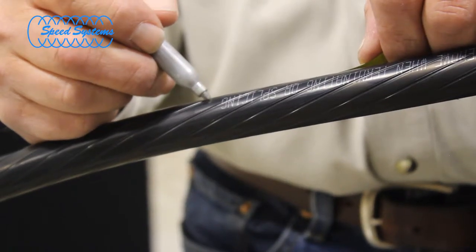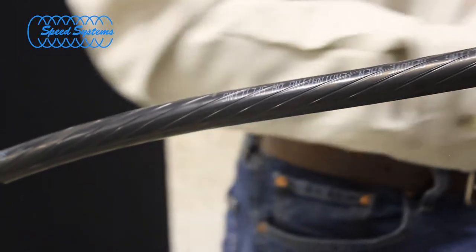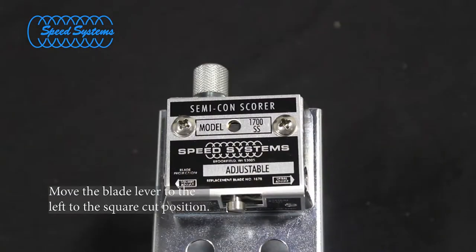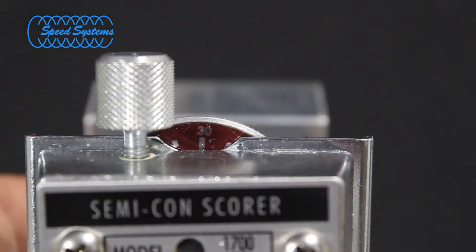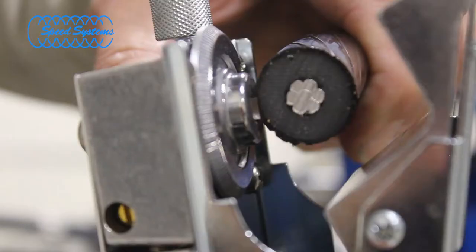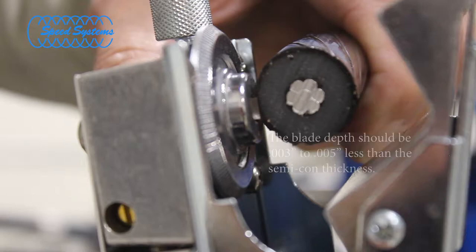Measure and mark the semi-con strip back according to the component manufacturer's instructions. Verify that the blade lever is in the square cut position and set the semi-con scorer blade depth to cut through most of the semi-con layer without cutting through to the insulation. Check the blade depth on a scrap piece of cable if one is available or by visually checking the blade at the end of the cable. The blade depth should be set to approximately 3 to 5 thousandths inch less than the semi-con thickness.